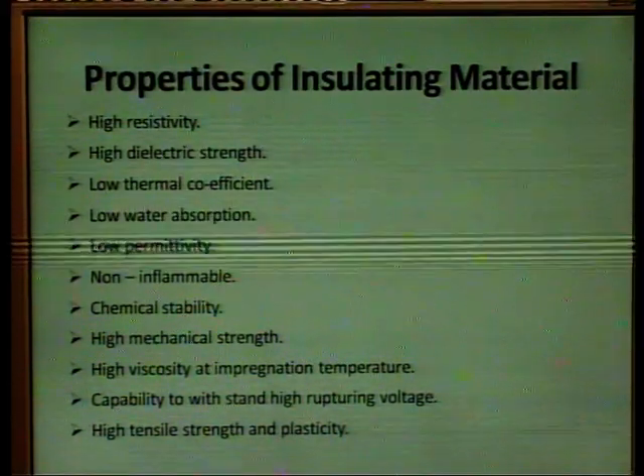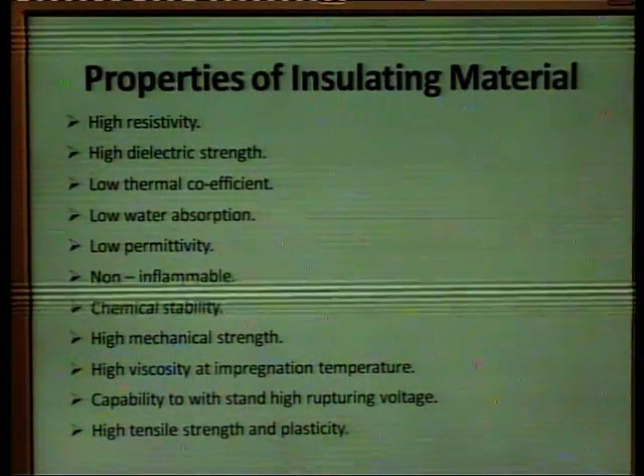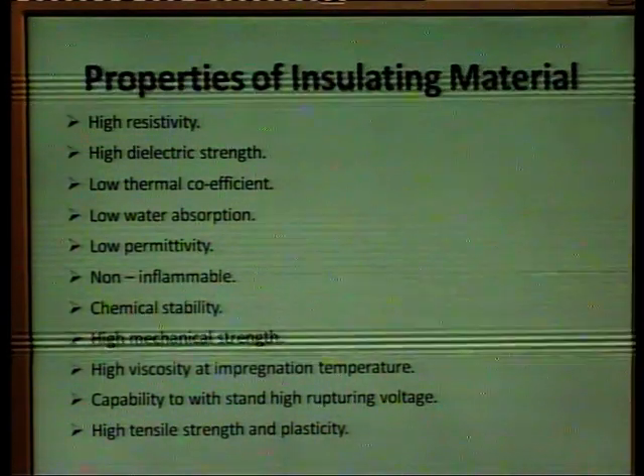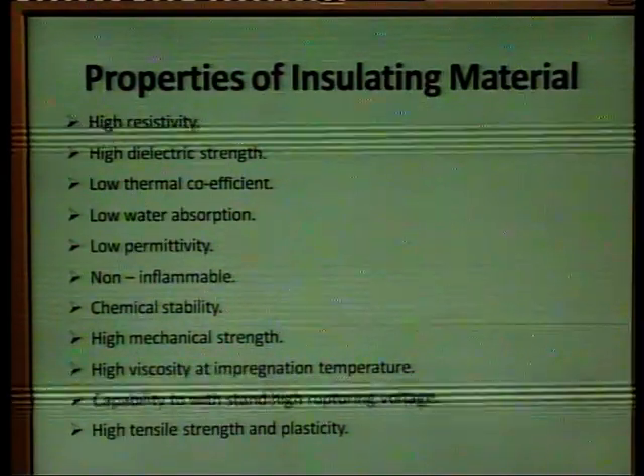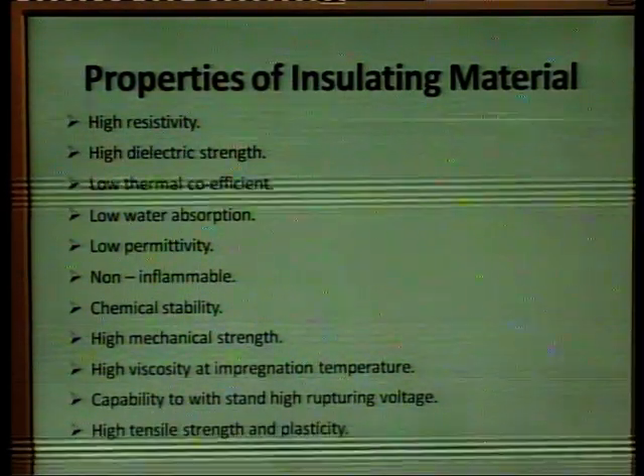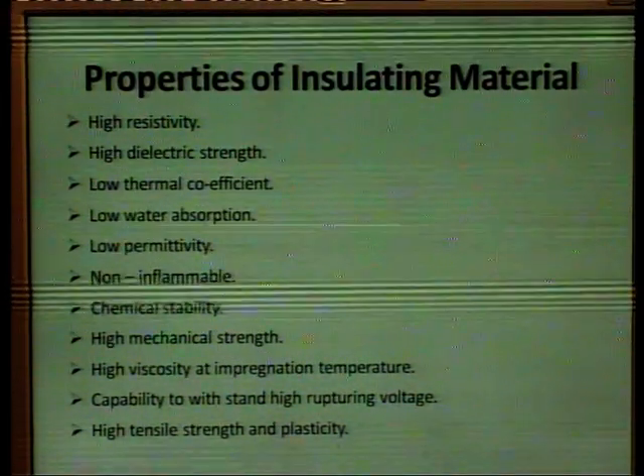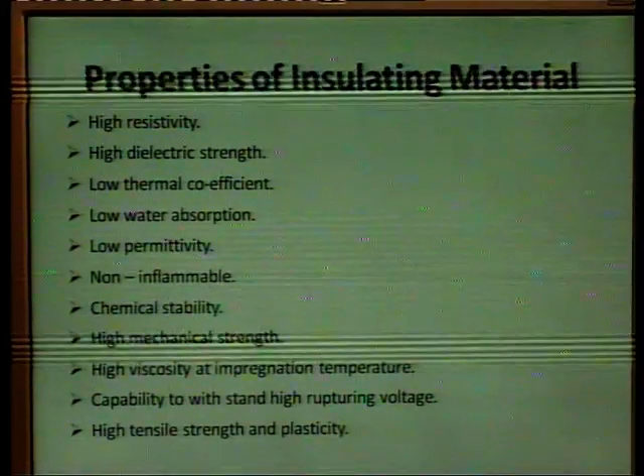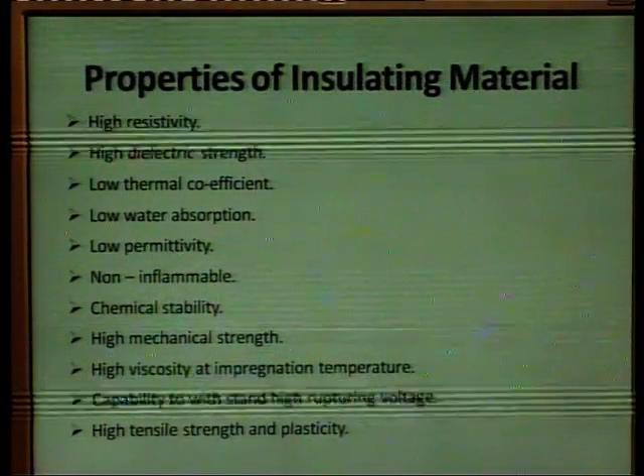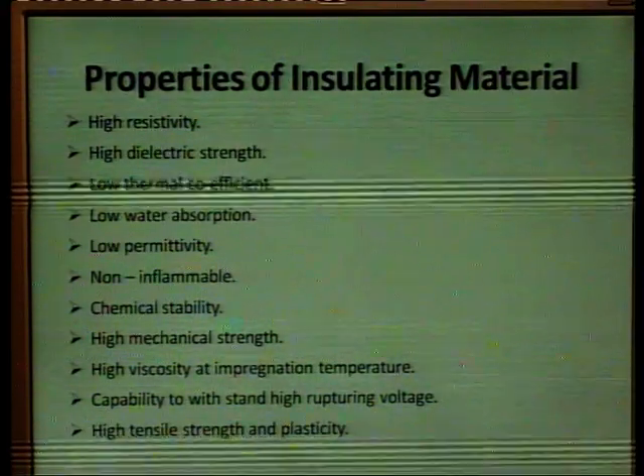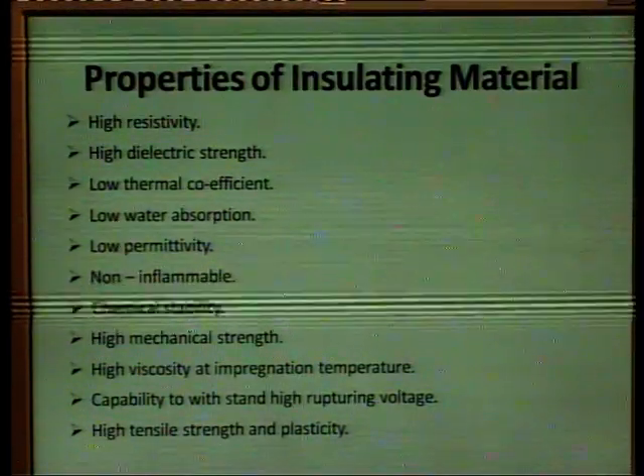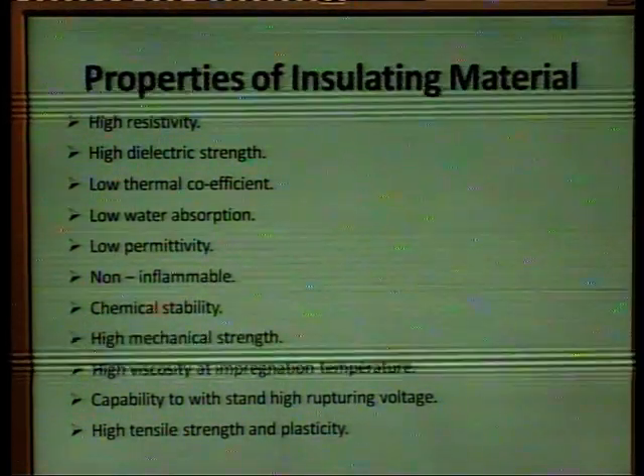Then we should have the properties of the insulating materials. What should be the properties of the insulating material? First is high resistivity. The resistivity of the insulating material should be high. Then it should have high dielectric strength so that it could withstand the voltages. Then the low thermal coefficient. The thermal coefficient of the material should be low so that it should not be melted. It should not melt at small temperatures.